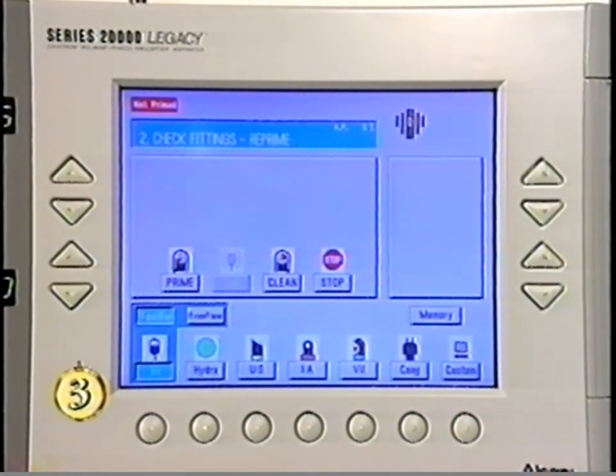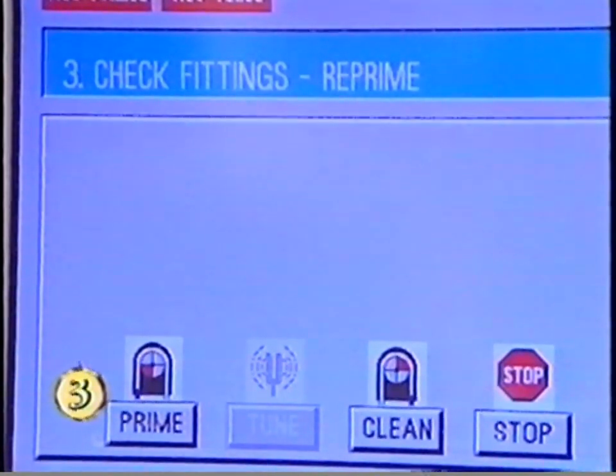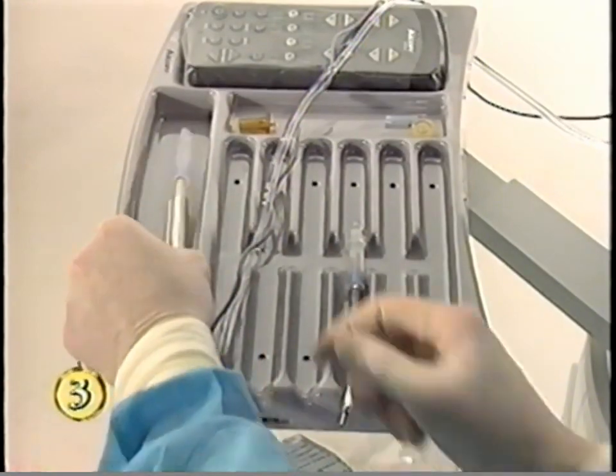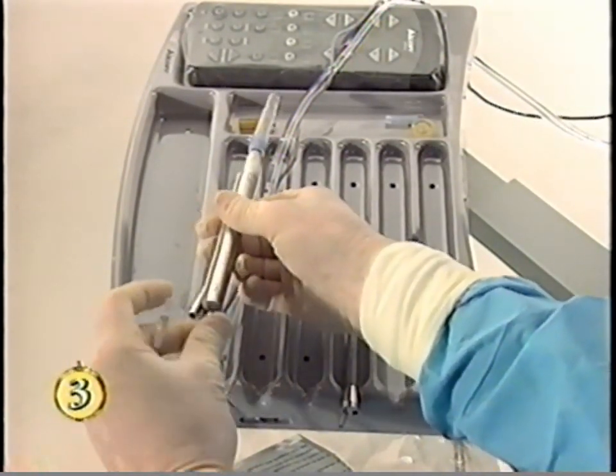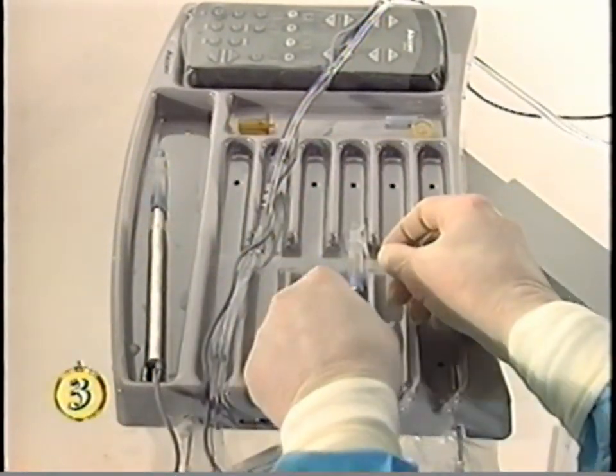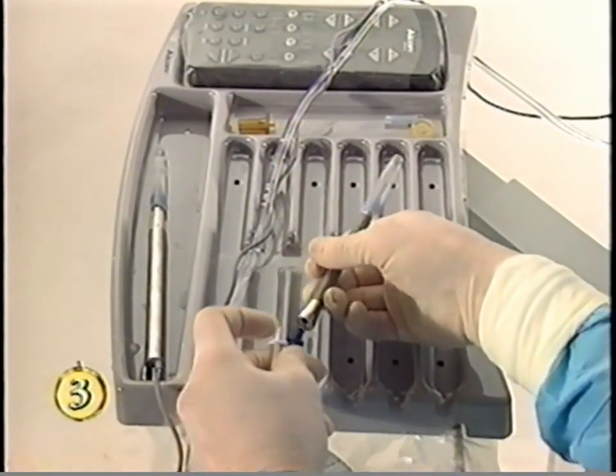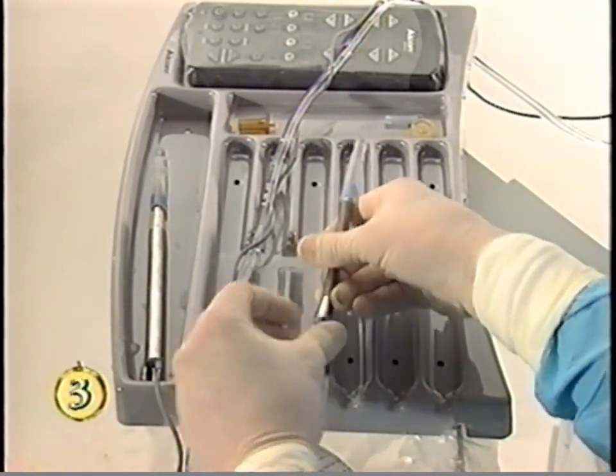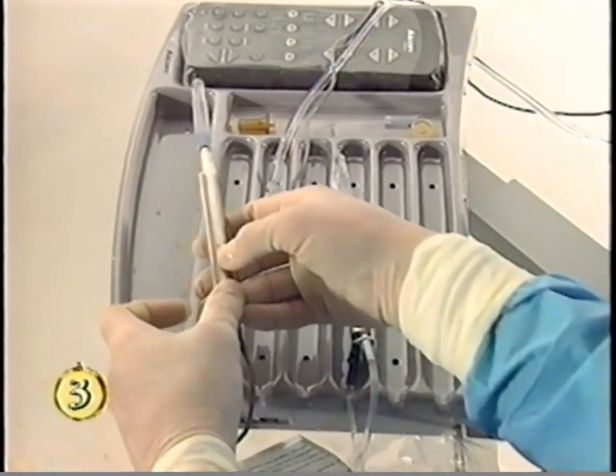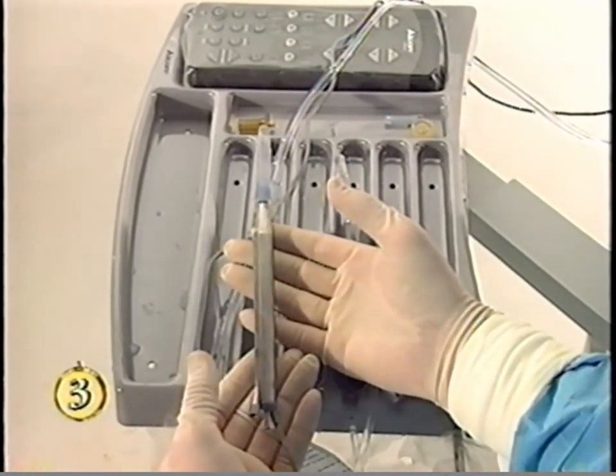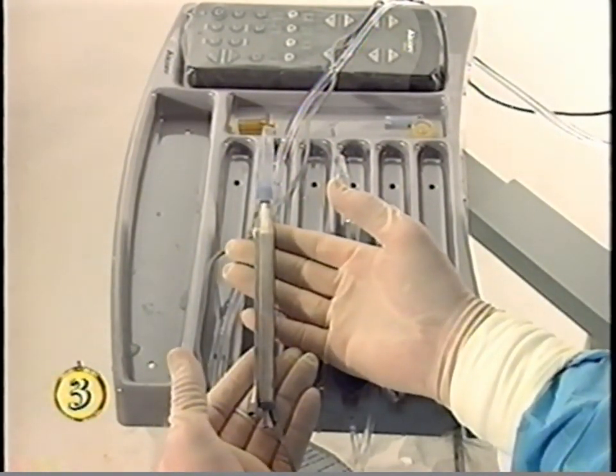After completing the test mode, the unit reverts to US phaco mode, and the IV bottle returns to its default or programmed height. When switching from a primed handpiece to another handpiece, always remember to leave the filled test chamber on the primed handpiece until aspiration and irrigation lines are attached and the handpiece is ready for use. This keeps the lines free of unwanted air.